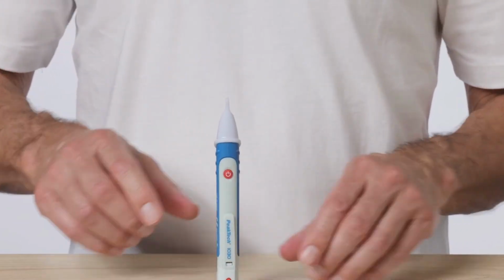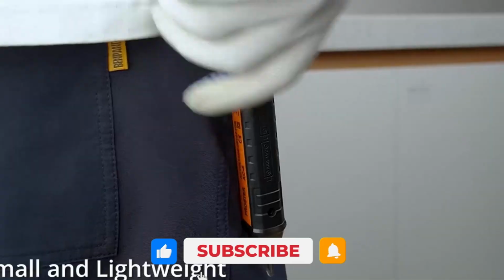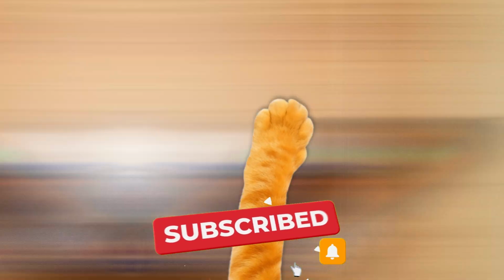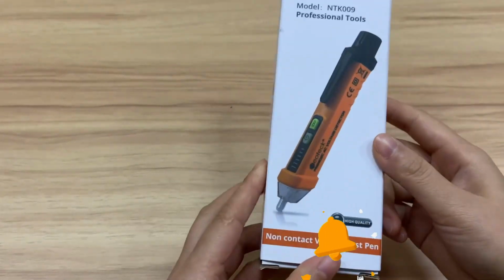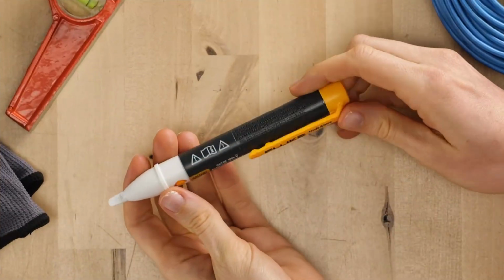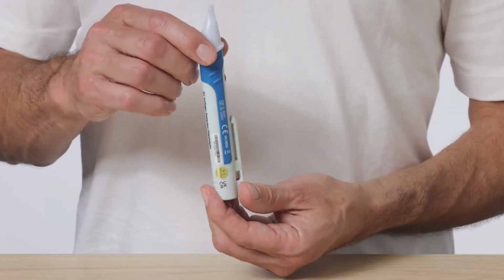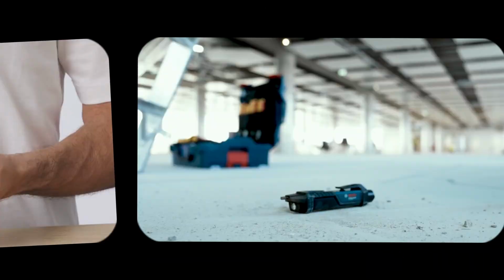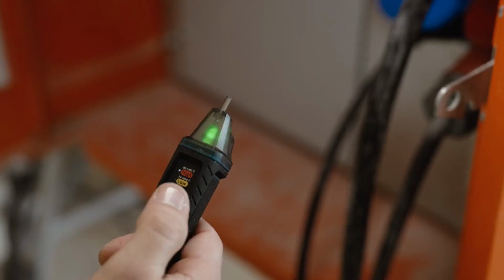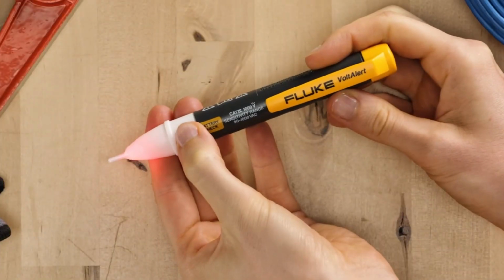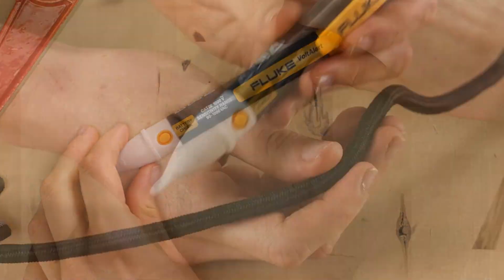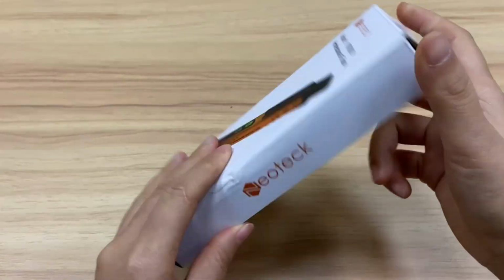Did you know a non-contact voltage detector can give you the all clear on a cable that's still live? These tools never touch the metal. They read the electric field around the conductor by capacitive coupling, and your body acts as the earth reference that completes the circuit. That's why a metal conduit can leave you with no warning at all, and why some models scream their heads off over an induced voltage that means nothing. The difference comes down to the threshold, the tip, and how the tool talks to you.